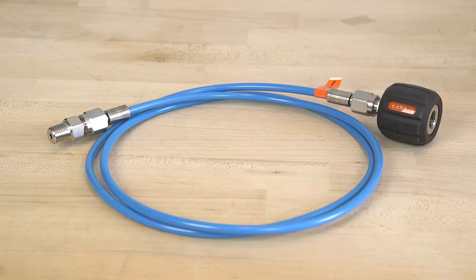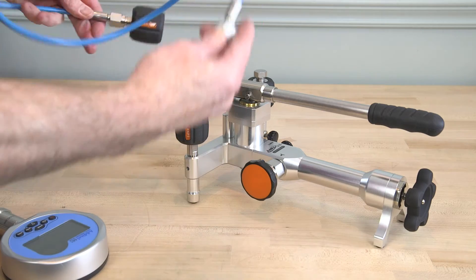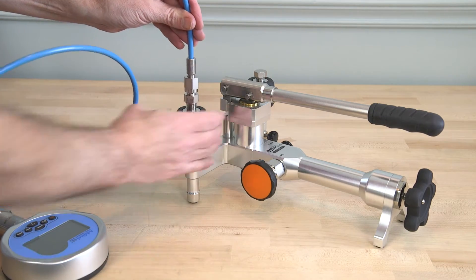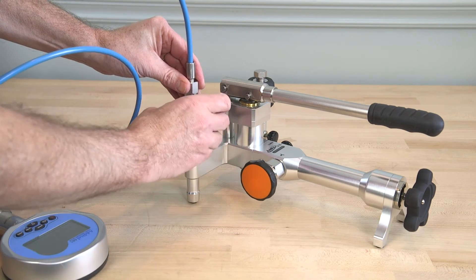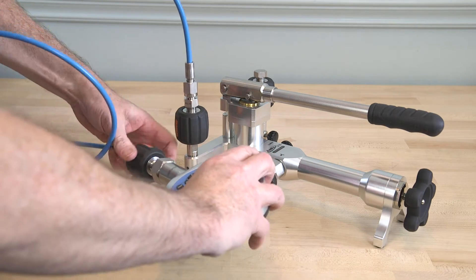The Additel 100 series hose test kits are designed to extend your pressure calibrations to a convenient location and to adapt from one pressure connection to another. Each test kit has 5 feet of flexible hose rated to 15,000 PSI, which connects a male NPT, BSP, or metric connector to a variety of female quick connectors.